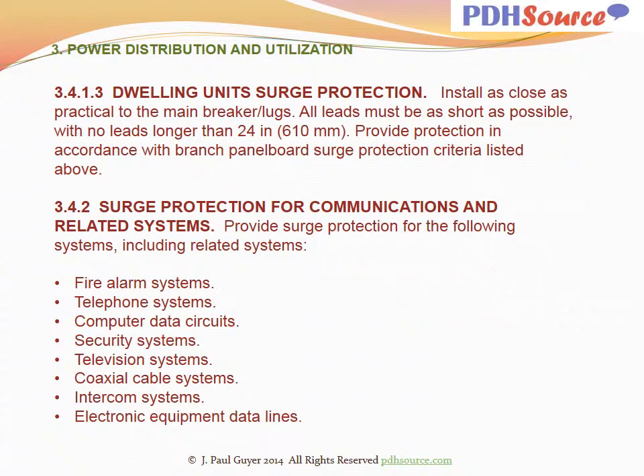Dwelling units protection: install as close as practical to the main breaker lugs. All leads must be as short as possible, with no leads longer than 24 inches. Provide protection in accordance with branch panel board surge protection criteria listed above.